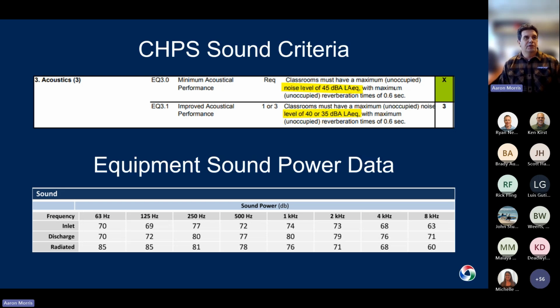Now, to know if you're going to be able to do that, you'll need to know the sound power from the equipment you're going to be using as your basis of design. So at the bottom, there's a little snip from a Daikin rooftop unit selection, where you can see we're looking at sound power in dB, and we have the 8 octave bands, and we're showing the inlet or return air duct connection sound power, the discharge or the supply air duct connection sound power, and then the radiated sound power that would be coming from the equipment.